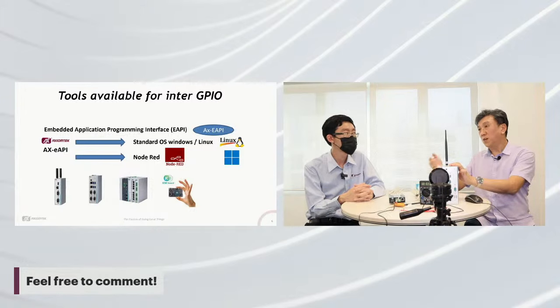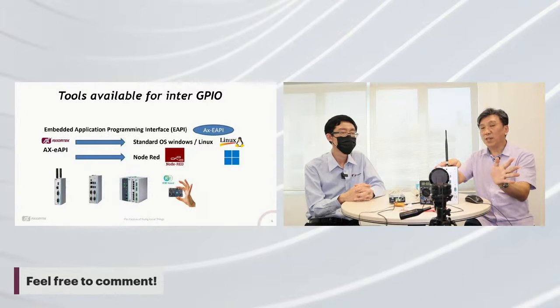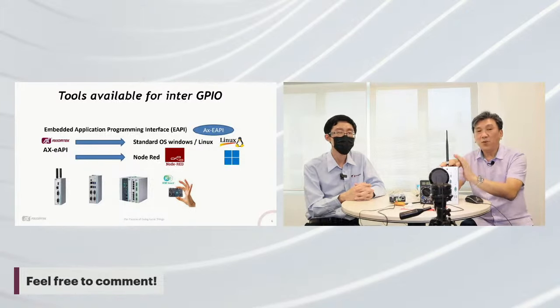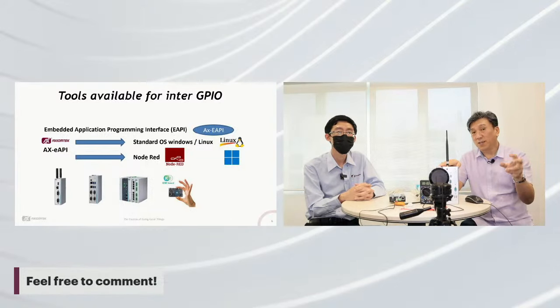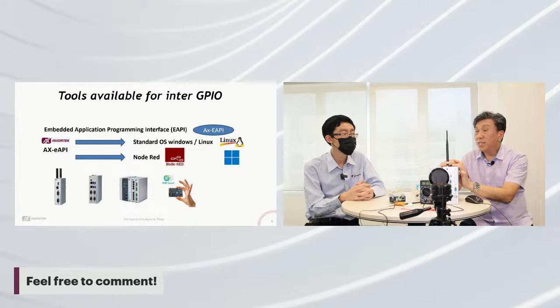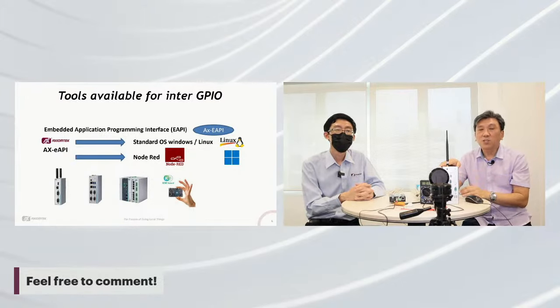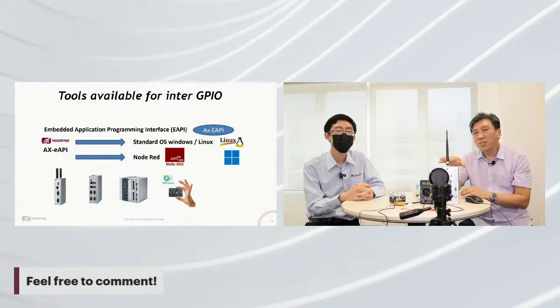This is also how AI edge applications for this kind of device are useful, where you plug in another daughter board and you are able to do, in fact, most of the I/O points. But of course, my point here is it is limited. We have some systems that already give you isolation in terms of output. We have certain models, I think the ICO 520. The latest gateway already comes with 8 inputs, 8 outputs. Those are isolated, the isolation is already built in for you. But in order to make the system lower cost, usually they are all digital inputs.